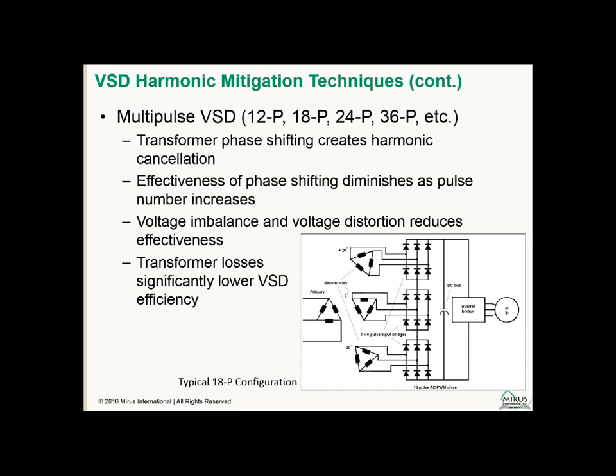again, the cancellation is dependent upon the phase angles being similar, and as soon as you introduce imbalance, the phase angles change on the harmonics. And also you're introducing additional losses. Transformers can be relatively lossy, so now you've reduced the overall efficiency of your VSD system.